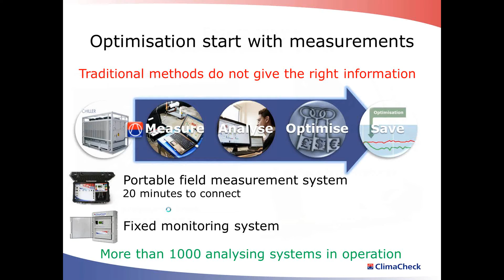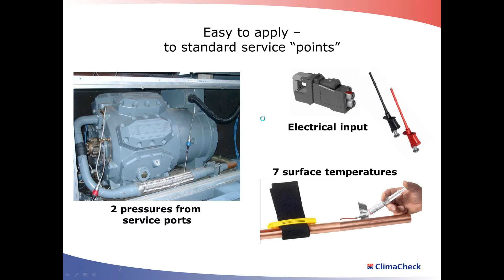The basic method for a standard system is that you connect two pressure sensors, the same high and low pressure that is used for any service. There are 7 temperatures that you apply with surface mounting on the tubes. And then you connect the electrical voltage and currents. Here it is shown in the flow chart, where you connect on the discharge of the compressor, the suction of the compressor, and the liquid line. And for references, you need to know what temperature conditions the condenser is working at and what temperature conditions the evaporator is working at, and then the active electrical input.